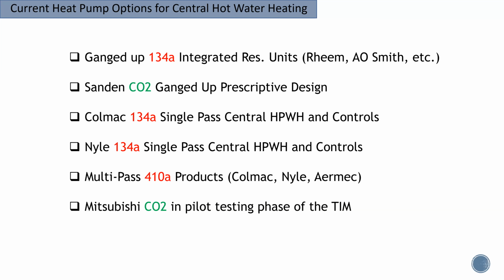The ganged-up 134A integrated residential units - this is an approach where you put several residential integrated heat pump water heaters together and feed, without recirc, close proximity apartment units off a single semi-decentralized bank of integrated units. The next option would be the ganged-up CO2 system, which also aligns with Title 24 prescriptive design.